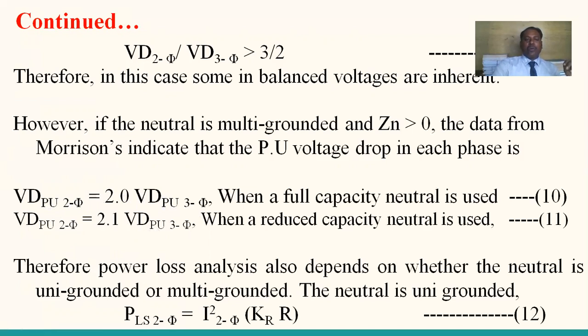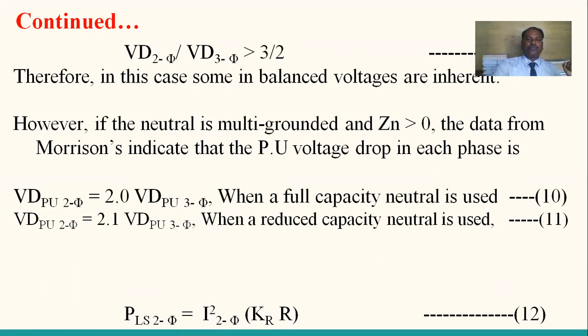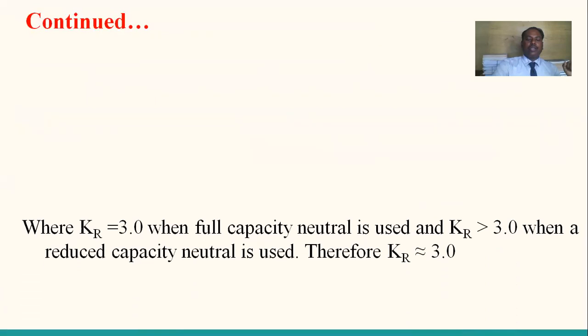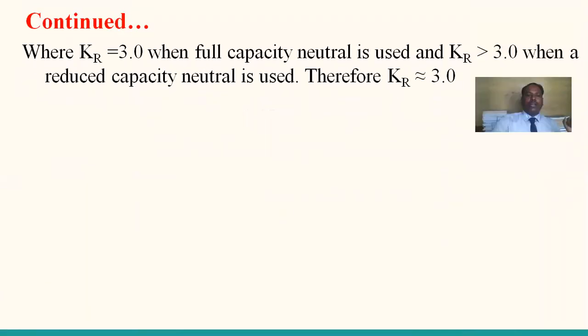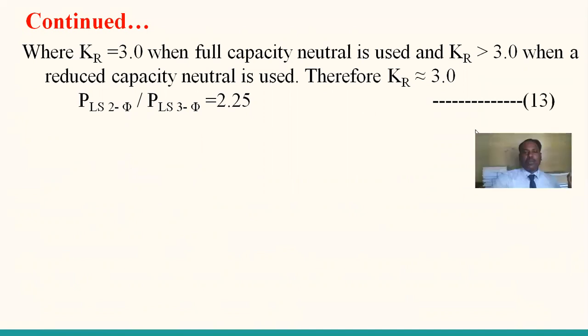Therefore, power loss analysis also depends on whether the neutral is uni-grounded or multi-grounded. If the neutral is uni-grounded, PLS two-phase is equal to I square two-phase into KR into R. Here KR is the conversion constant, where KR is equal to 3.0 when a full capacity neutral is used and KR is greater than 3.0 when a reduced capacity neutral is used. So KR should be approximately taken as 3. So PLS two-phase by PLS three-phase is equal to 2.25. This is equation number 13.